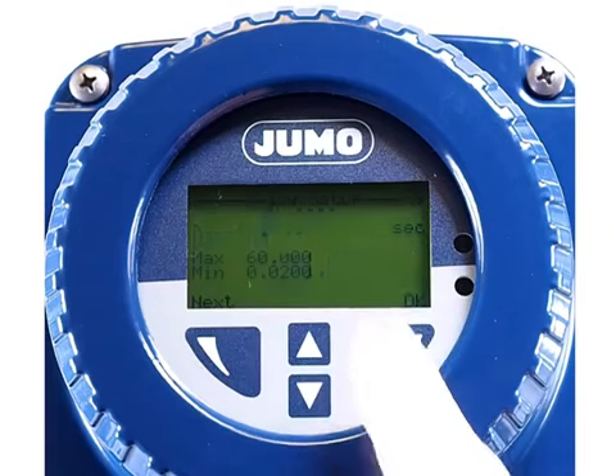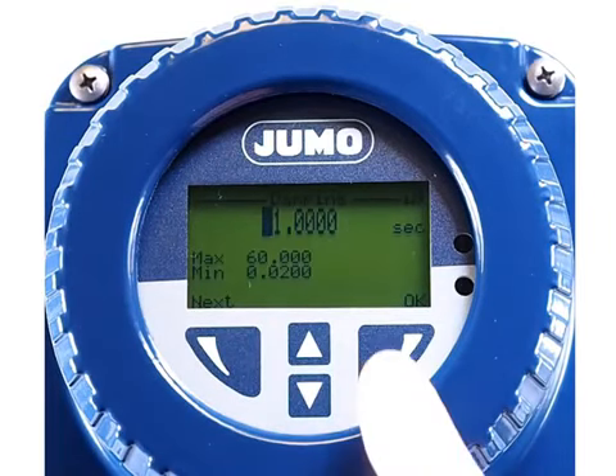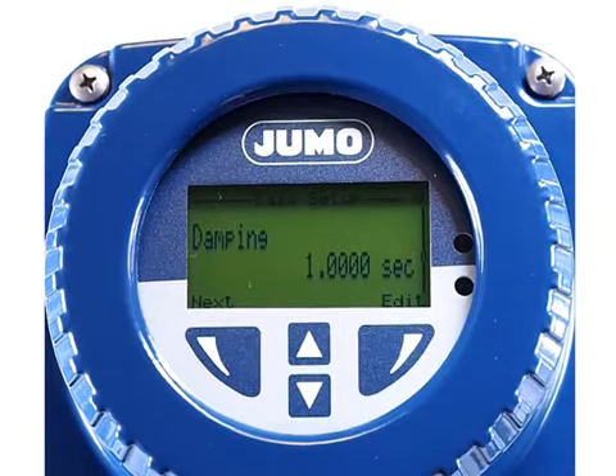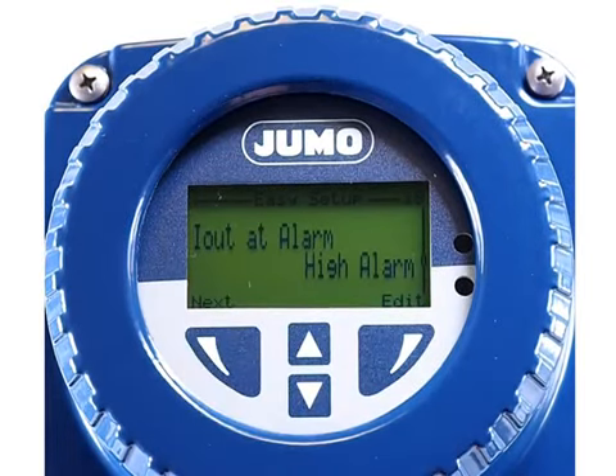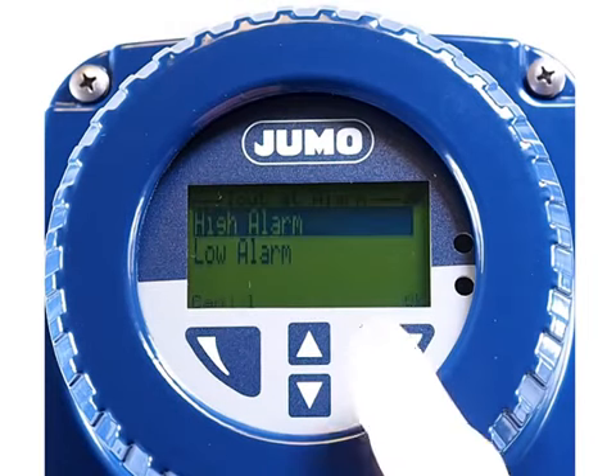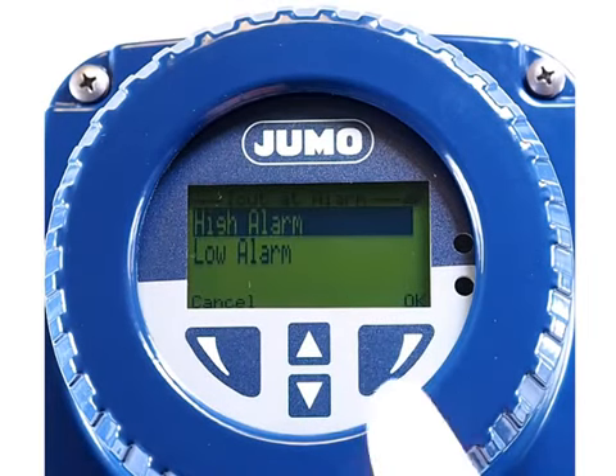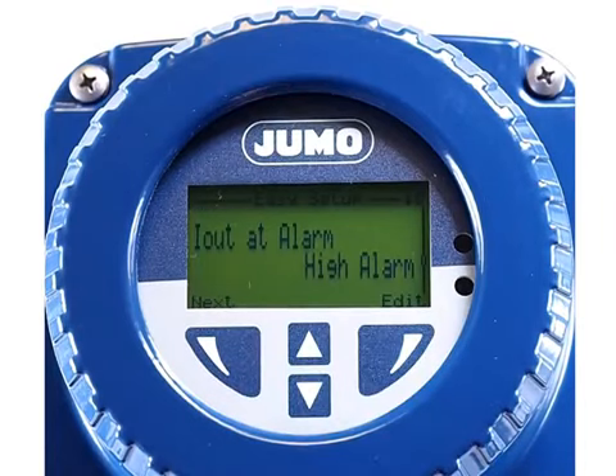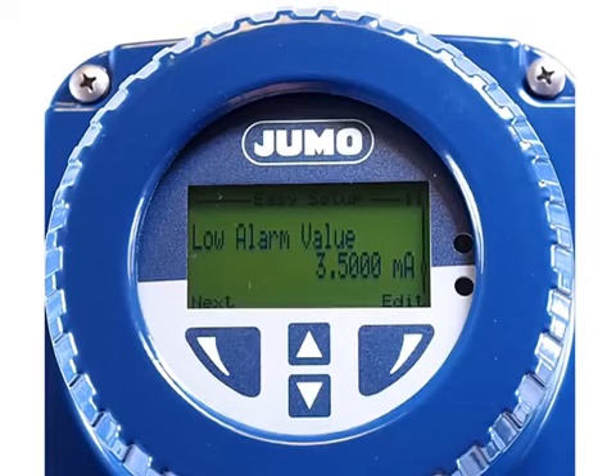Next, the damping can be changed. If disturbing fluctuations of the measured value occur, the damping time can be increased, which extends updating the measured value. If an error occurs, for example when exceeding the measuring range or with empty pipe detection activated, in addition to a binary alarm output, the current output can be set to a defined value, which can be interpreted by the field device. At first we choose the alarm signal. In the following two steps, the defined values for the currents are set.